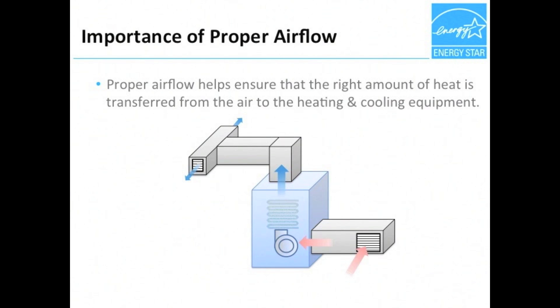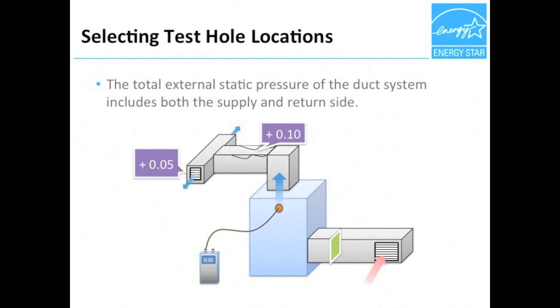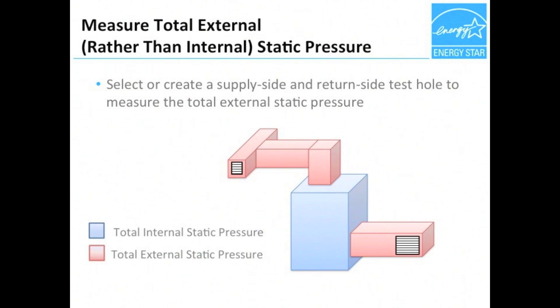Static pressure can be used to determine the airflow of the HVAC fan, so let's discuss how you actually measure the static pressure. Perhaps the most challenging part of this process is determining where to locate the holes to measure static pressure. To get the total external static pressure, you need to measure the positive pressure on the supply side of the fan and the negative pressure on the return side of the fan. This means you'll need to make two holes or use existing holes.